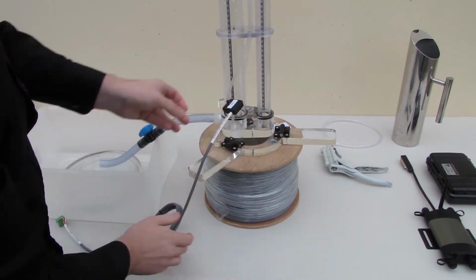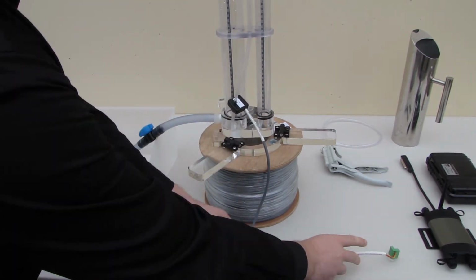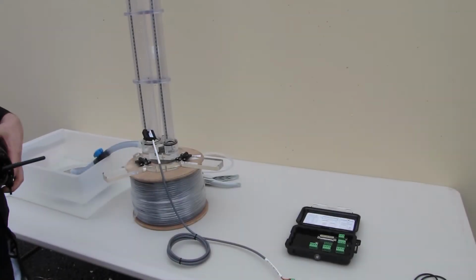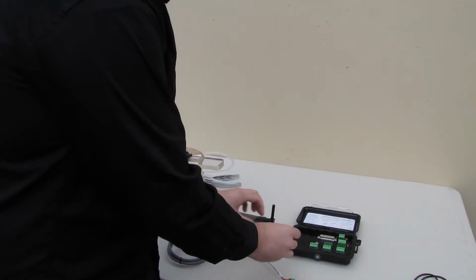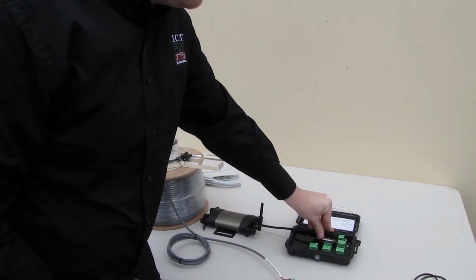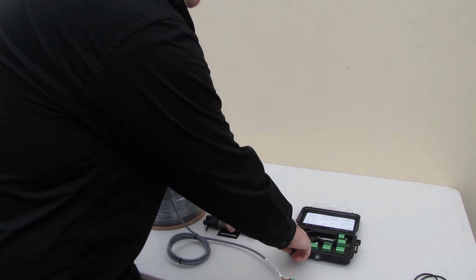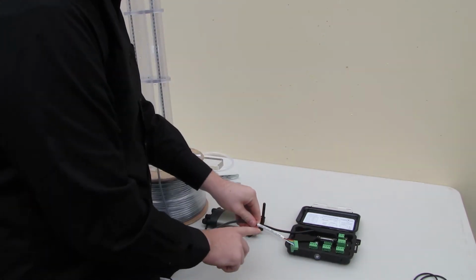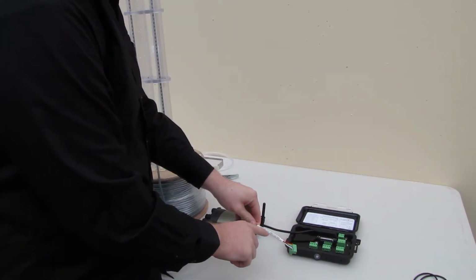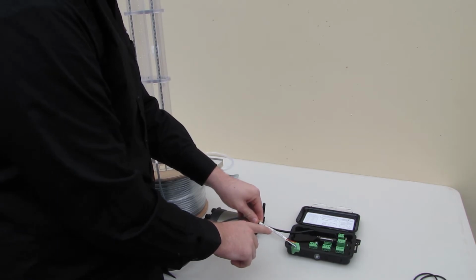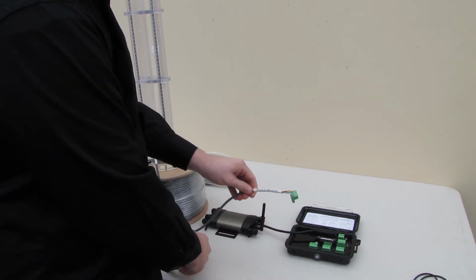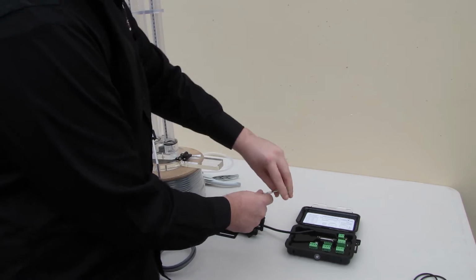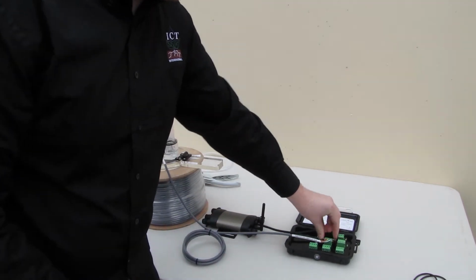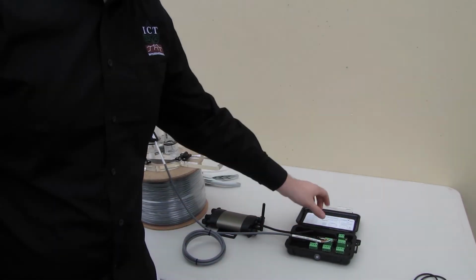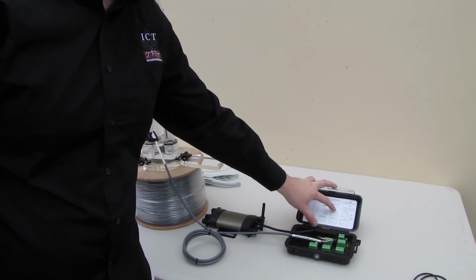Now connect the AIM1 logger to the differential breakout box. Then plug in the pressure transducer. You will notice on the sensor label will be the serial number of the AIM1, the channel it connects to, and the model of the cable assembly. Normally, a single AIM1 sensor will start at channel 1. The green connectors are keyed, so they only fit in one way. A connection label is shown in the breakout box lid for reference.